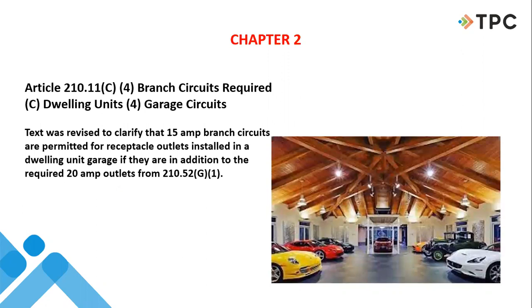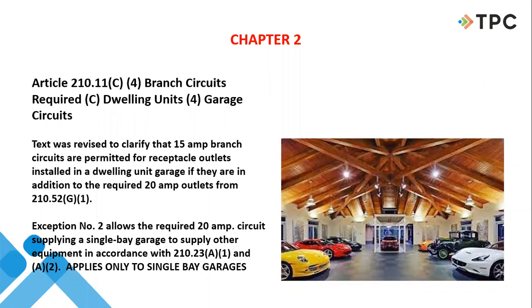What do we have here? Clarifying that 15 amp branch circuits are permitted without all the code caveats. 20 amp receptacles in a garage, fine. Well, they're saying here you can have 15 amp branch circuits. They're perfectly fine as long as they're in addition to the required 20 amp outlets. And then they even have a little caveat in here that exception number 2 allows the required 20 amp circuit supplying a single bay garage to supply other equipment. But that only applies to single bay garages.